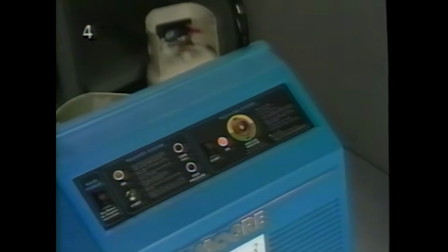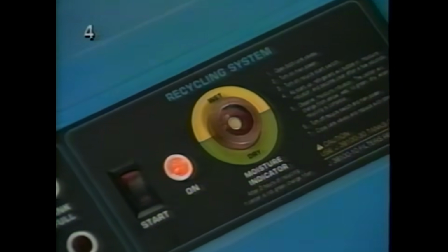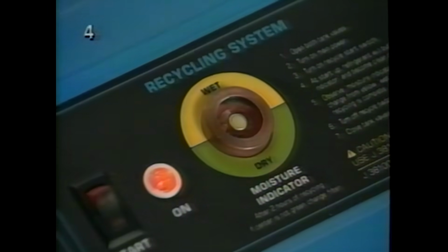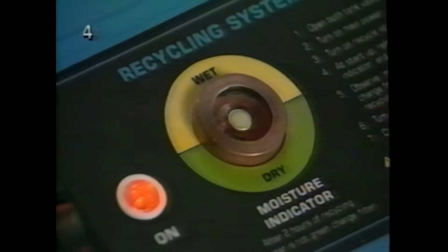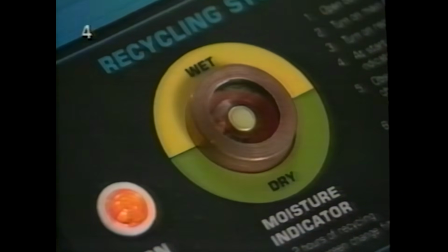To recycle refrigerant, open both valves on the recovery tank. Turn on the recycle start switch. The light should come on, along with the compressor. You can see refrigerant going through the moisture indicator as the station starts up. After a few seconds, you'll see the bubbles clear out if there's enough refrigerant to perform an efficient recycling operation.